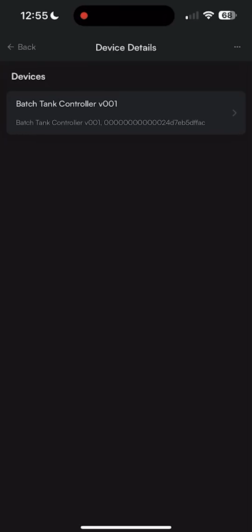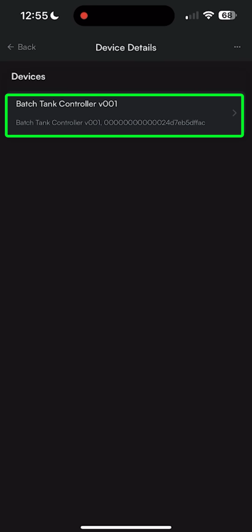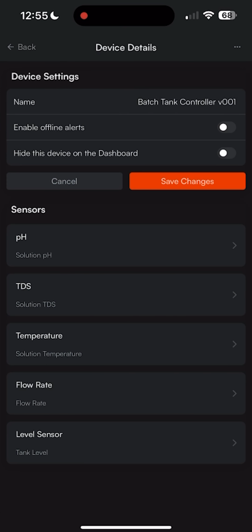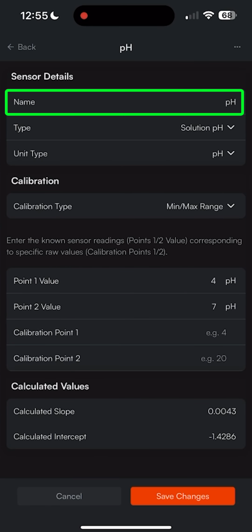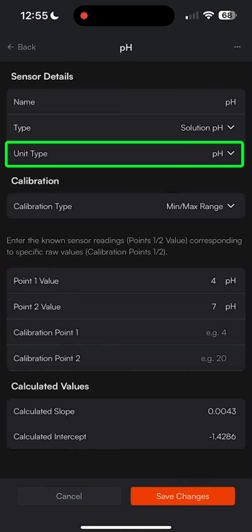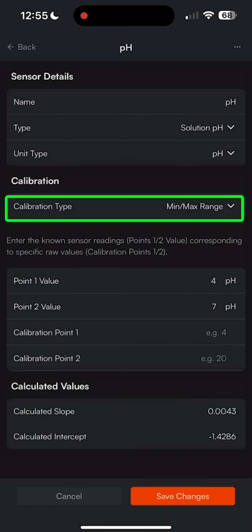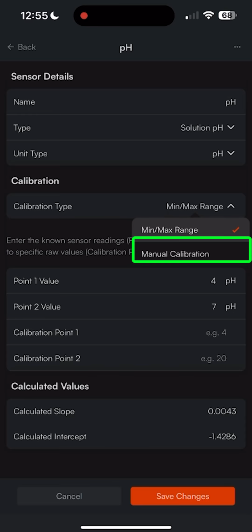To calibrate a sensor input, start by going to the Hardware tab and selecting a device that has calibratable inputs, like a batch tank module or an analog input. Select the sensor that you want to calibrate. In this case, we'll start with pH. On this page, we can specify the name of the sensor, the type, the unit type, and then the calibration type. There are two types of calibrations, a min-max range and a manual calibration.